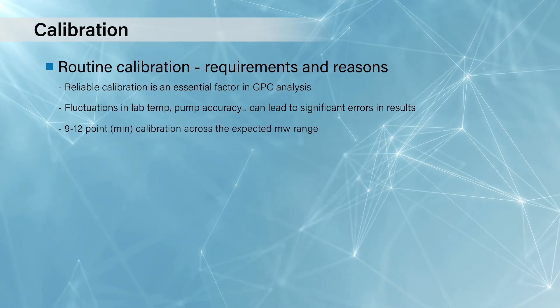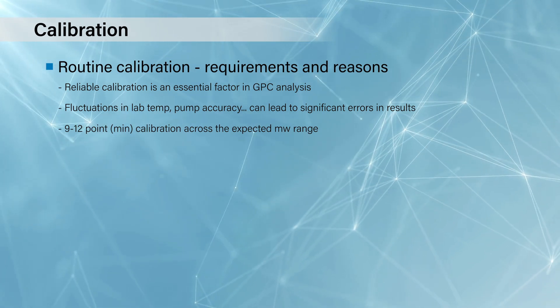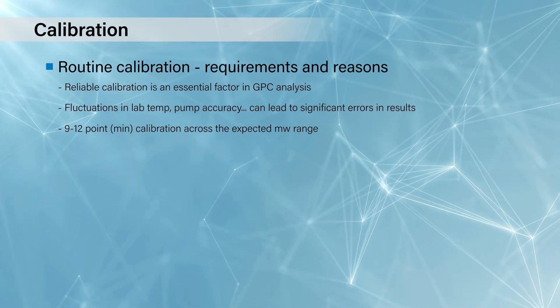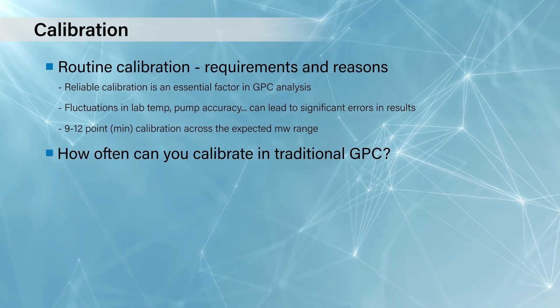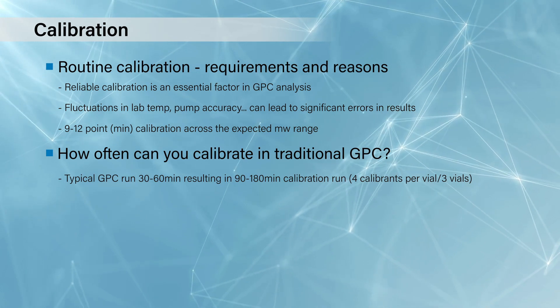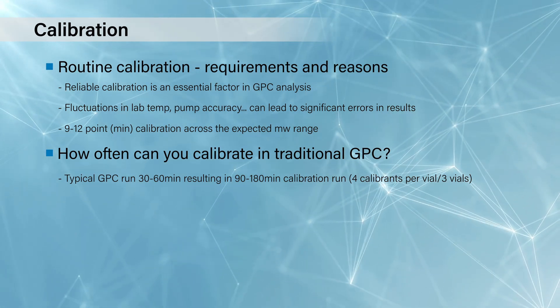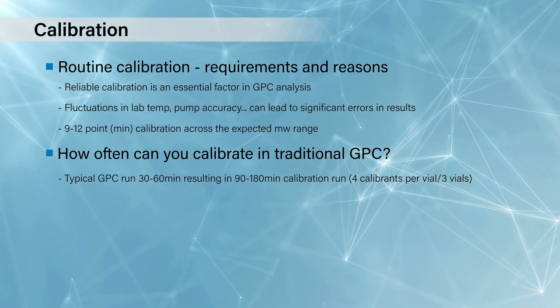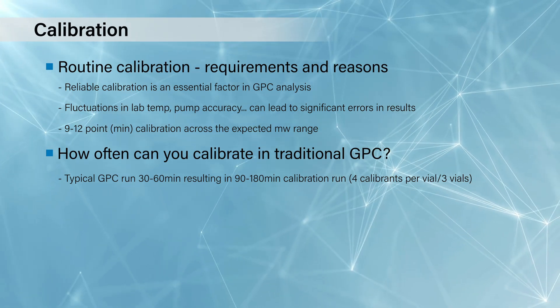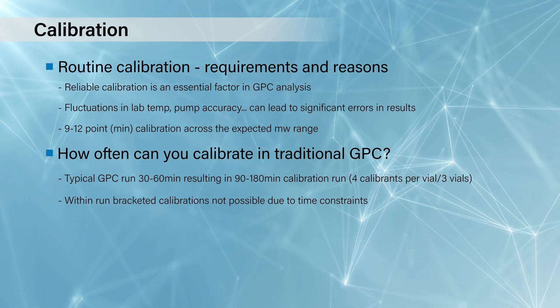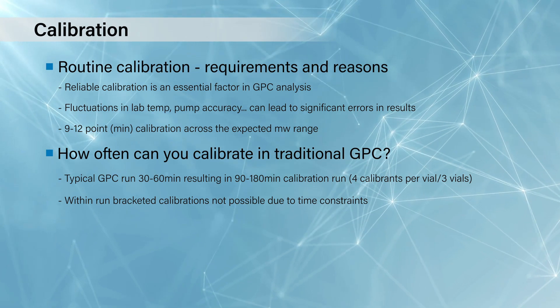We traditionally look for between nine and 12 point calibration as a minimum across the expected molecular weight range of your intended analyte. How often do you do it? It's always an interesting question to ask users — it's never as frequent as maybe they would like, due to the time taken to actually calibrate the system. If you think about traditional GPC runtime, it's between 30 and 60 minutes. If you have sets of calibrants with normally four per vial — the optimal situation — that's still three vials, so you can be looking at a few hours to perform a calibration. People don't tend to run bracketed calibrations or regular calibrations due to these time constraints.